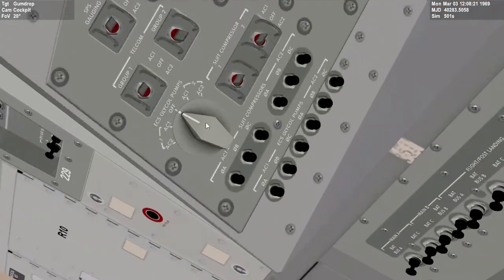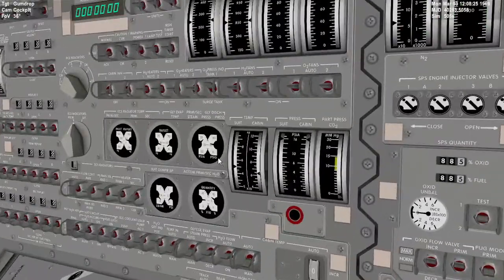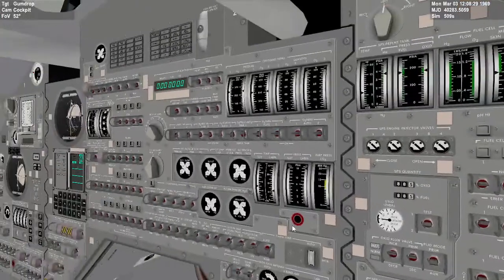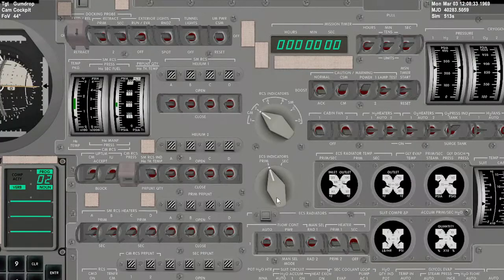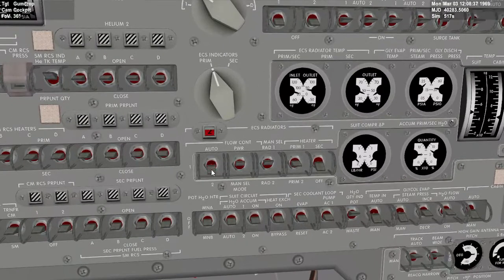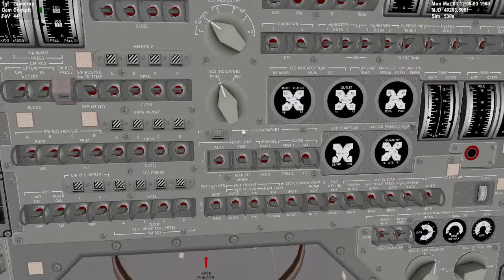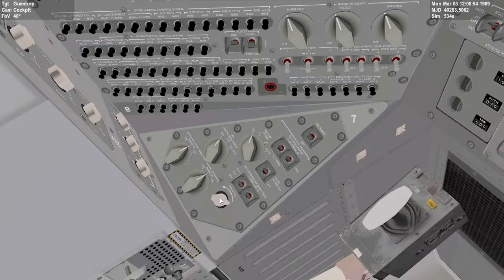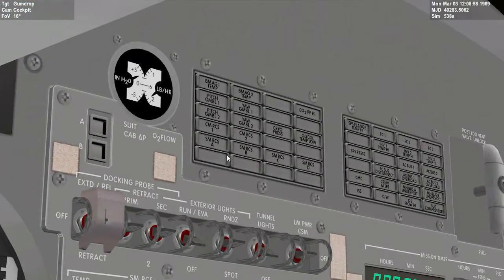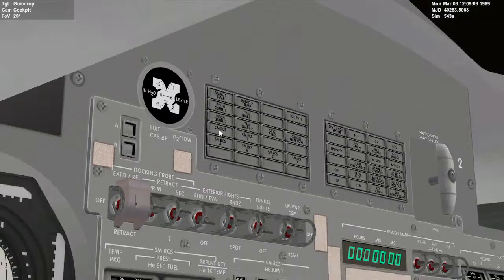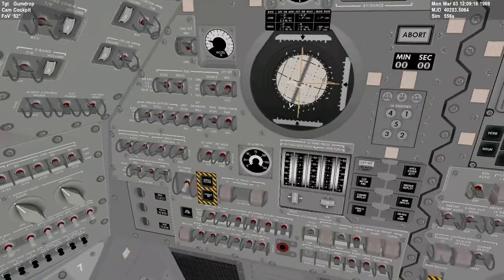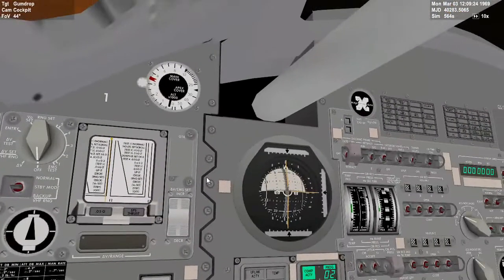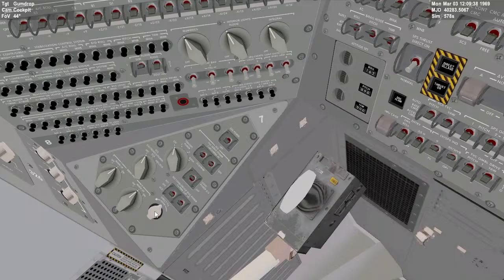Glycol pumps AC2, glycol pump 2 AC1. Pressure stable. Pump 1 AC1. Pressure stable. Radiator flow control check. Flow controller power. Flow controller 2. And flow controller to primary auto. Flow control power off. Direct O2 comes up to 0.4. Should be about right there. Gotta wait for that to come up, probably. This is just past half open. But we still have to wait for the O2 flow to come up. Let's adjust it to about here.